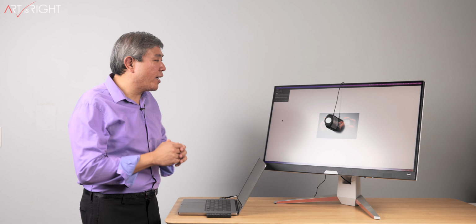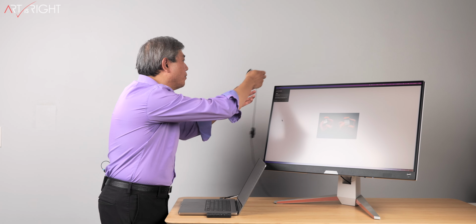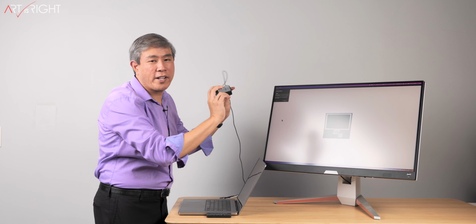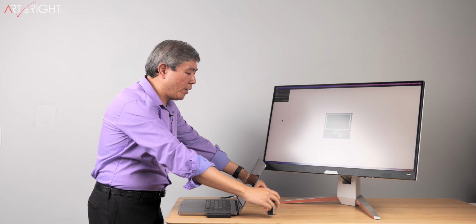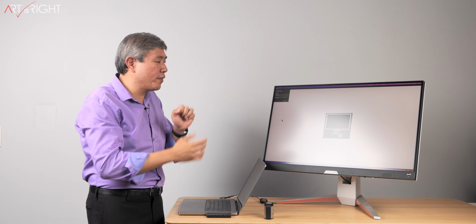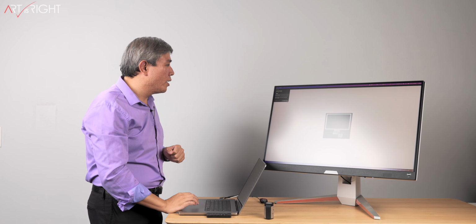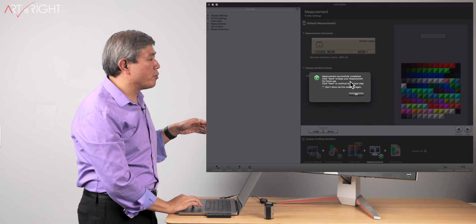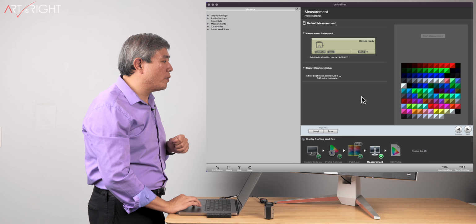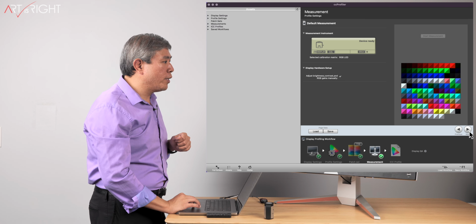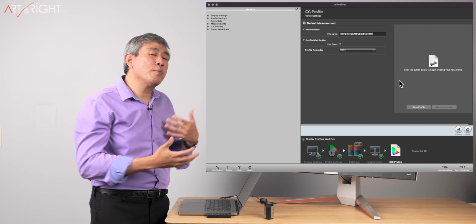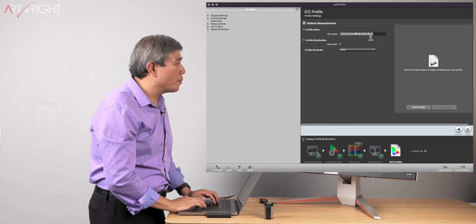Okay, so we're done with the calibration. I'll take the sensor off from the display. In fact, I should just leave it there, but I'm going to take it off anyway because the program wants the cover to be fully on. I'll click on Next. It says that the measurement was successful, which is good. That's what we want. And what I will do is click on Next. And this is where I would name the profile.